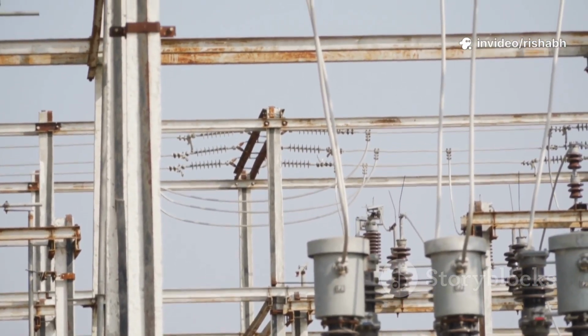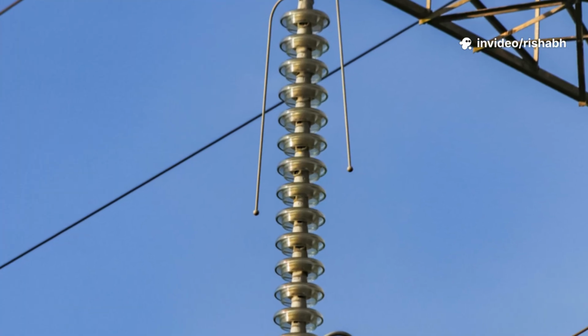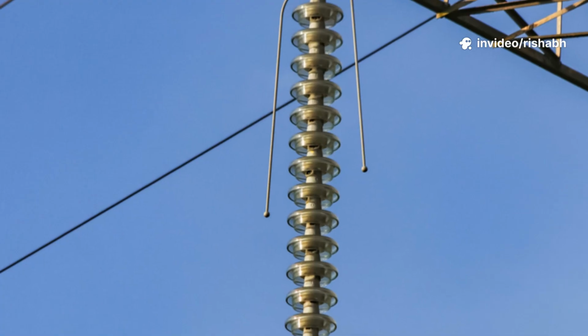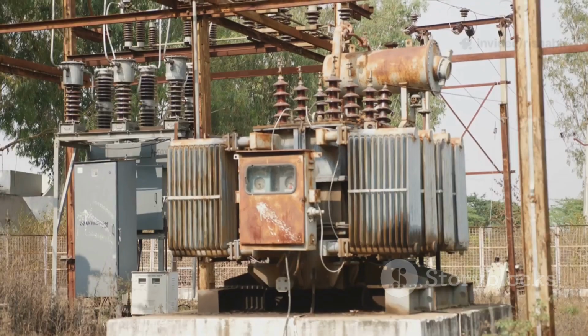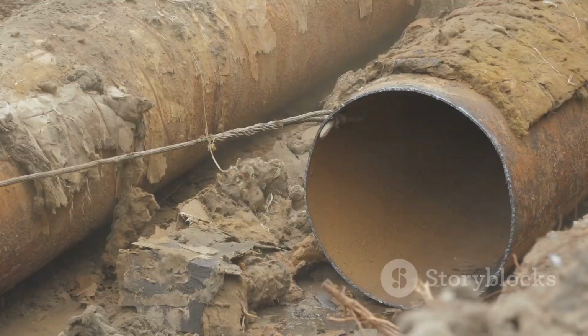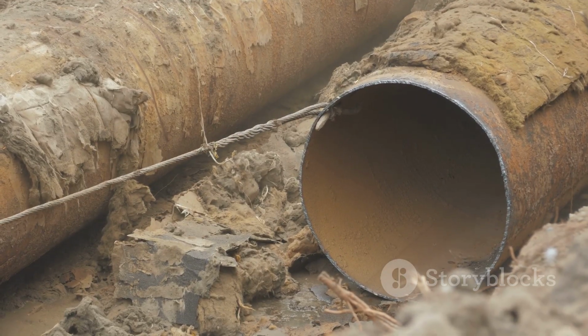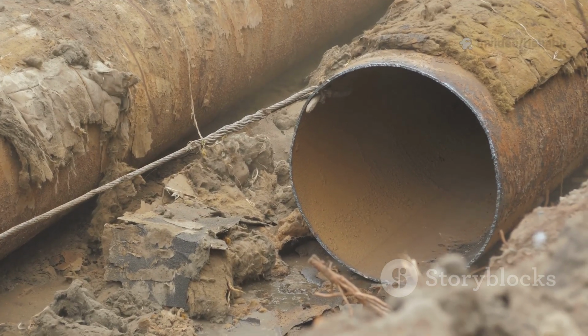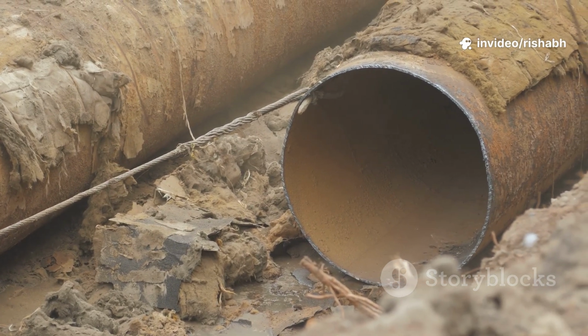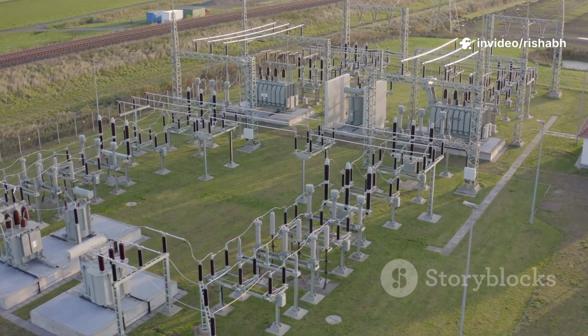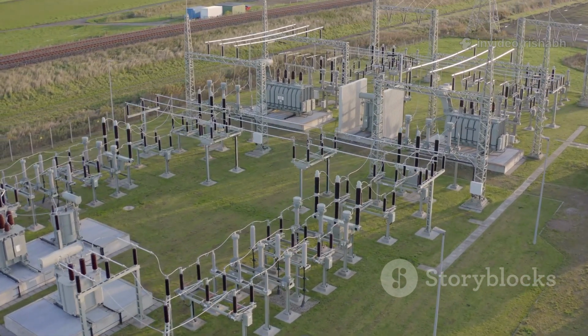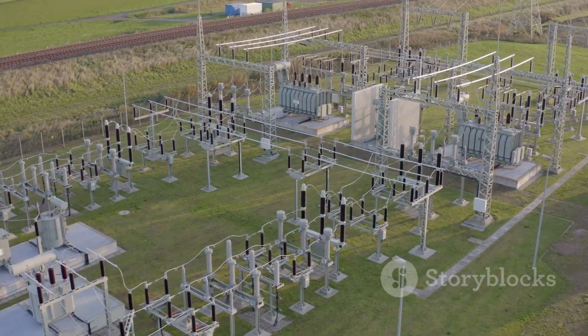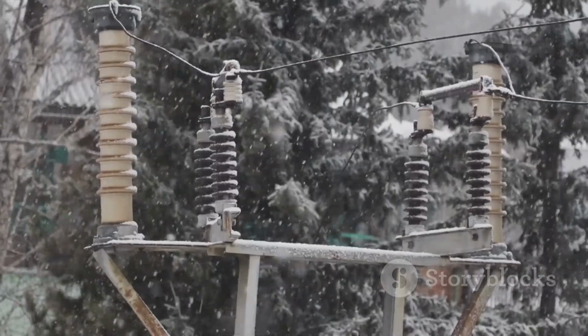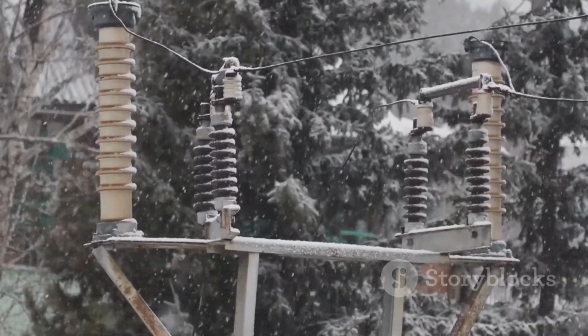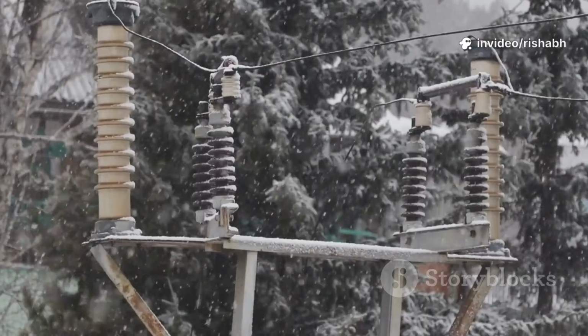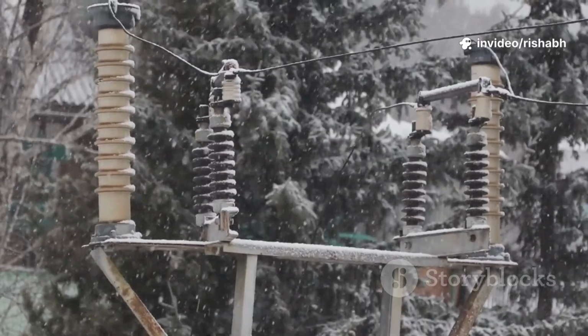of thousands of volts. The external part of the bushing, exposed to the air, has a series of sheds or skirts. These are not just for decoration. They increase the creepage distance, the shortest path for an electrical current to track along the surface of the insulator. In rainy or polluted conditions, a layer of contamination on the bushing surface can become conductive. The long, convoluted path created by the sheds prevents a flashover from occurring, ensuring reliability even in harsh weather.